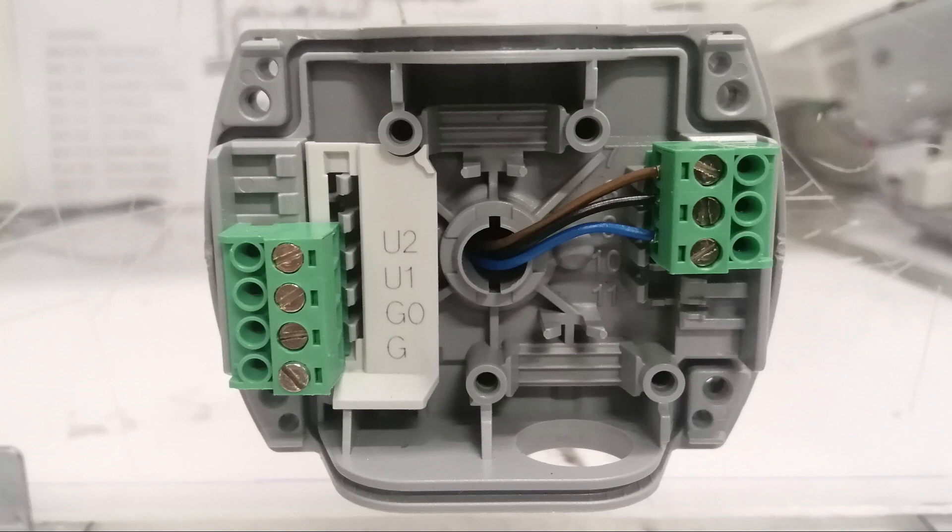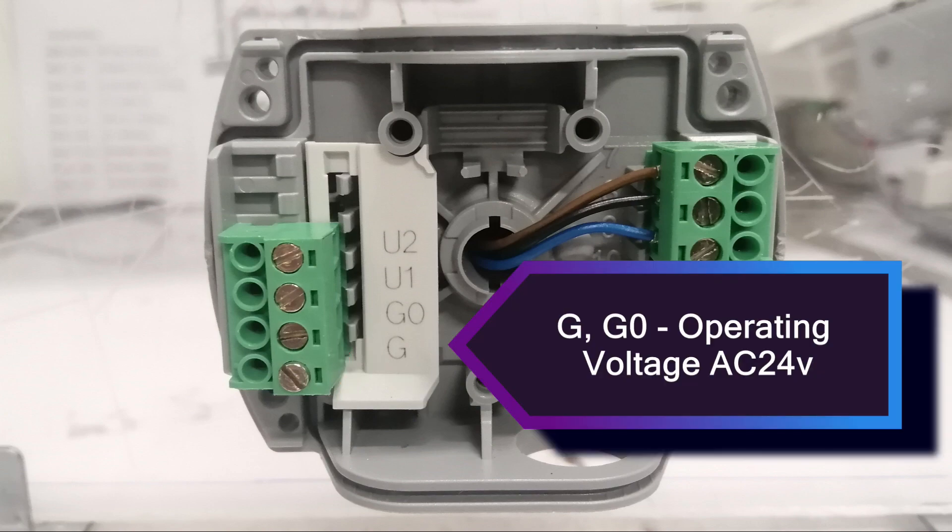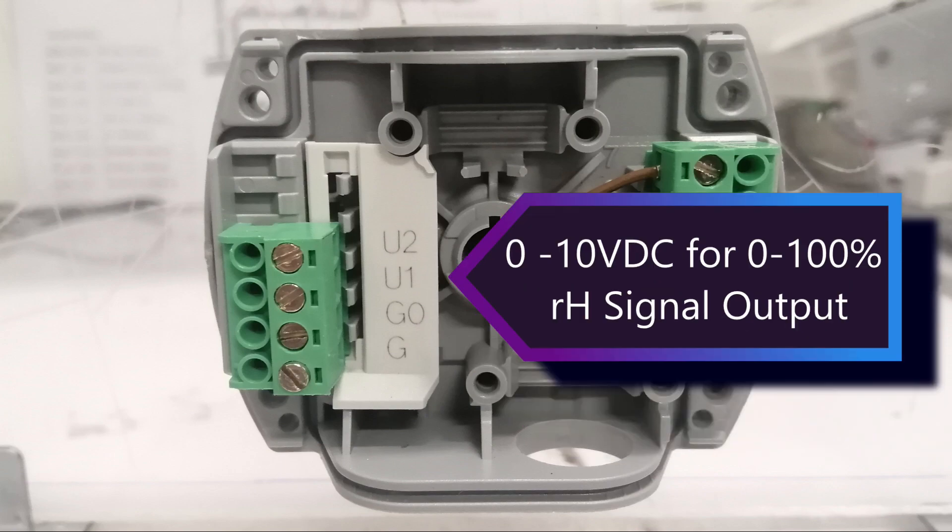This is where the terminal blocks are located. This terminal block is for the sensing element and the other terminal block is for the power supply input and signal output. G and G0 are terminals for operating voltage, U1 is for humidity signal output, and U2 is for temperature signal output.